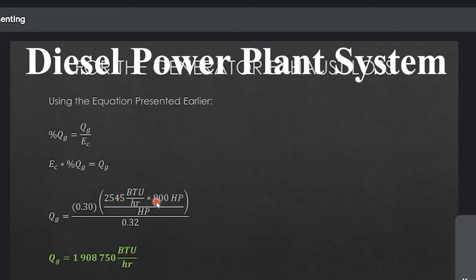Convert natin yung 800 horsepower into BTU per hour, multiply natin yun by the percent of generator exhaust loss, which is 30%, divided by the brake thermal efficiency. So ang makukuha natin ngayon na generator exhaust loss ay 1,908,750 BTU per hour. Ito yung generator exhaust loss natin.